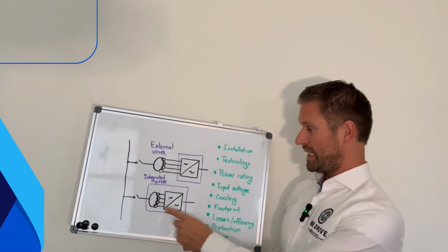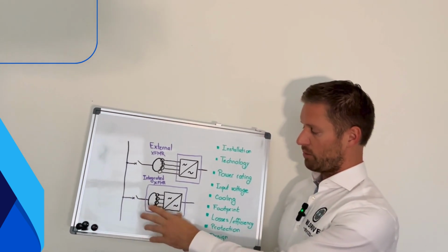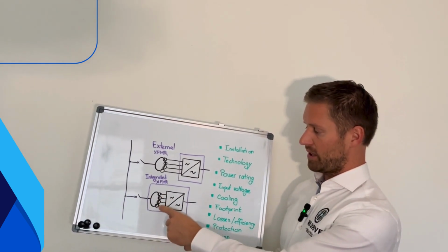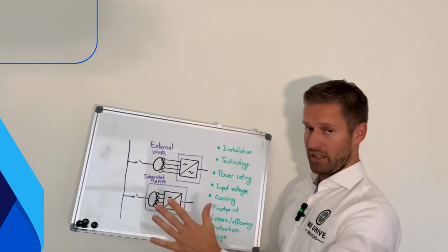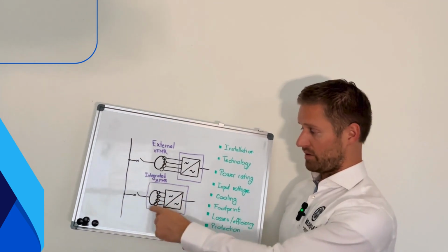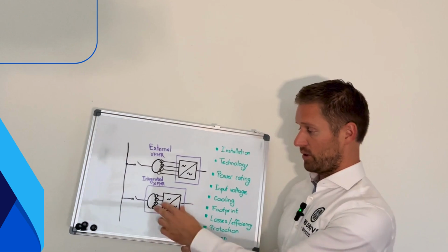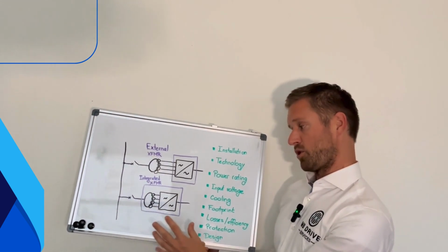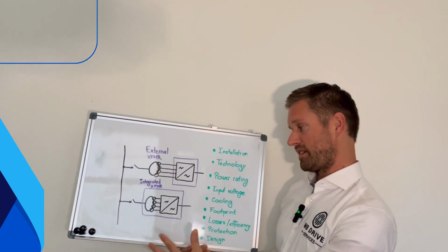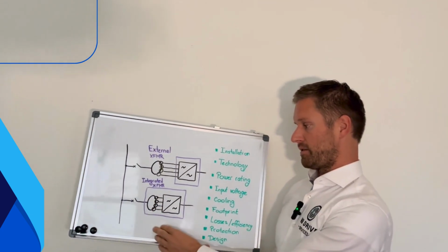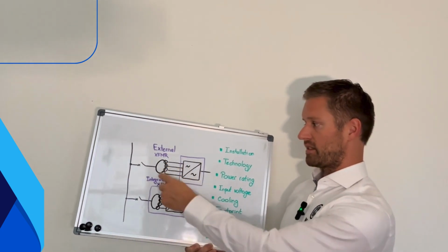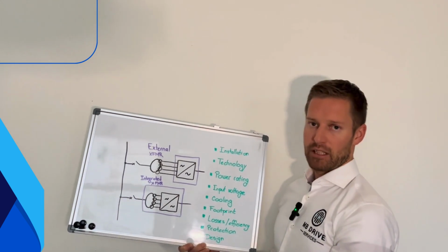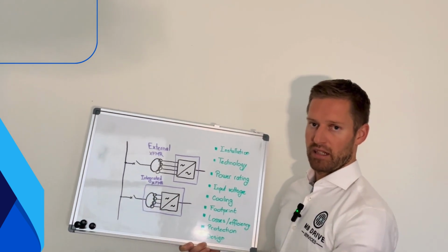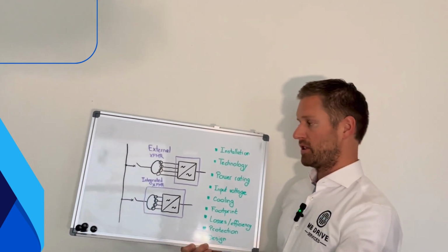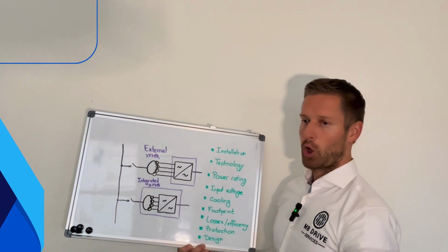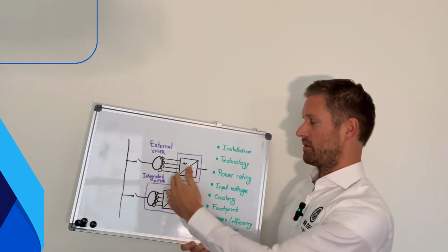Losses and efficiency. Let's say this transformer has medium efficiency, the losses might be a little bit higher in percentage. It's because of the small footprint, because we are optimizing for footprint and not for efficiency. So small transformer, a little bit of saving on the material, and a little bit more losses. On the external transformer, we are basically free to optimize for footprint or for efficiency or simply for cost, whatever we want.